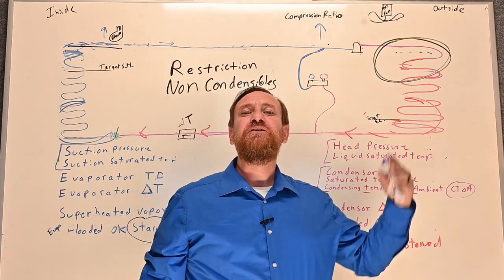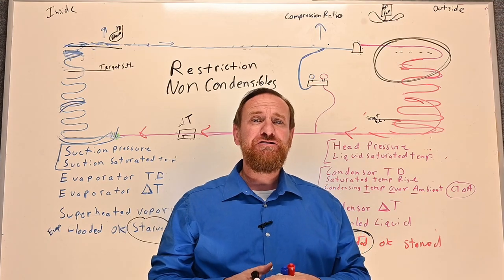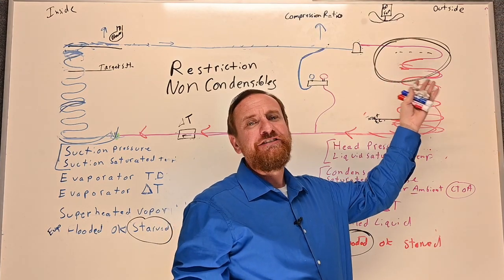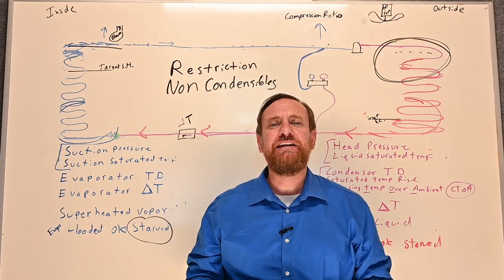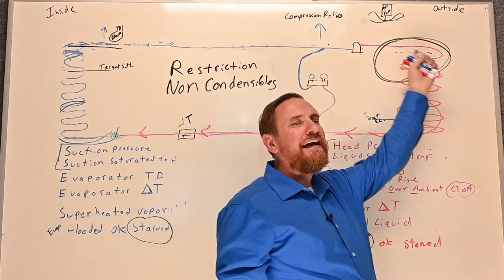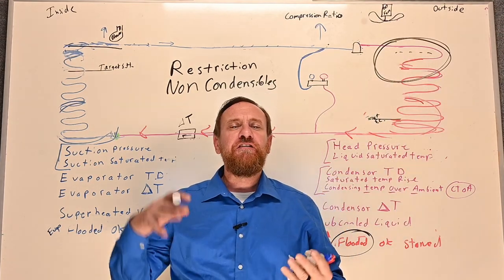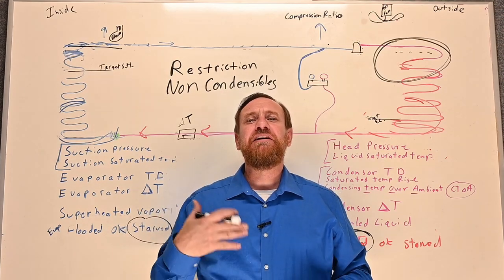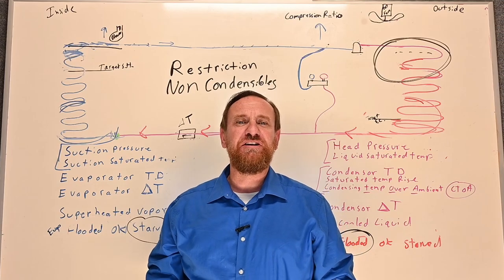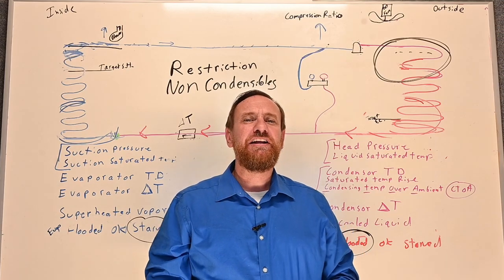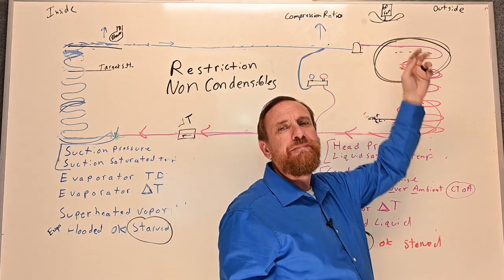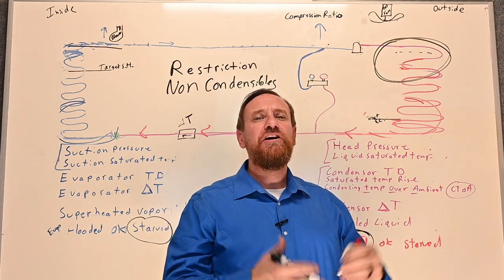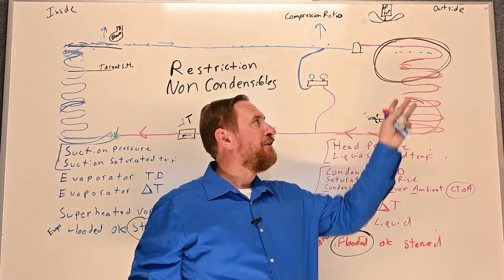It's not legal to vent non-condensibles that way because you'd lose refrigerant, and with blended refrigerants it would cause fractionation. Non-condensibles collect at the top of the condensing unit or recovery tank. On your EPA exam, the Class III purge unit is always located at the top of the condensing unit — it purges out these contaminants.